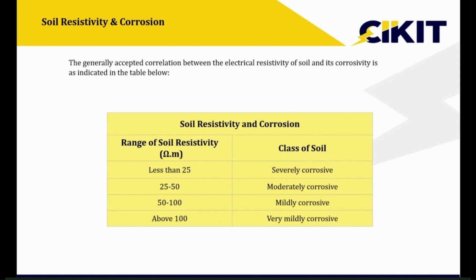So the lower the soil resistivity, the greater the corrosion rate. That is the reason they mention that if the soil resistivity is less than 25 ohm meter, it will be severely corrosive. On the other hand, if the soil resistivity is more than 100 ohm meter, then the minerals and salts in that particular soil are much lesser. Since the minerals and salts are much lesser, the corrosion rate will be much lesser.